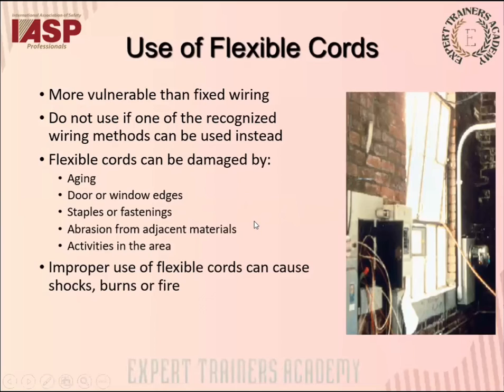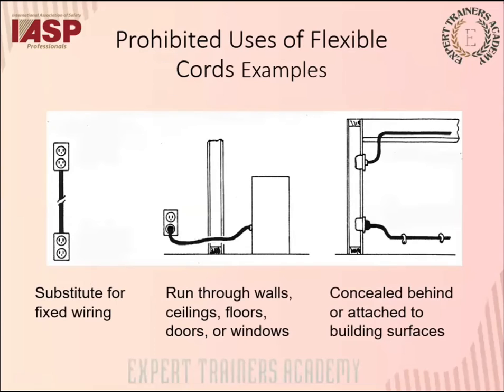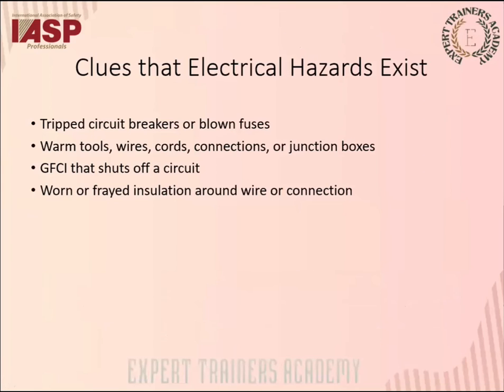Or other activities carried out in that area could cause damage to the insulation, which leaves a live electrical cable that you might come in contact with, leading to electrical shock. So improper use of flexible cords can cause shock, burns, or fire. Prohibited uses of flexible cords, examples: substitute for fixed wiring, run through walls. See, basically you attach them on the ceiling or the walls.